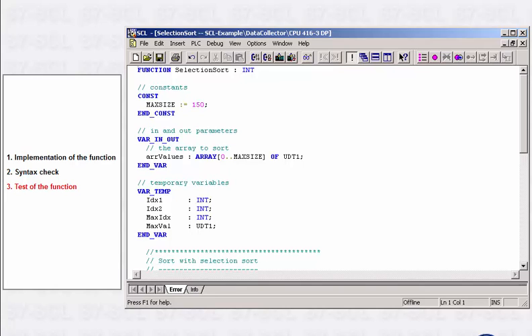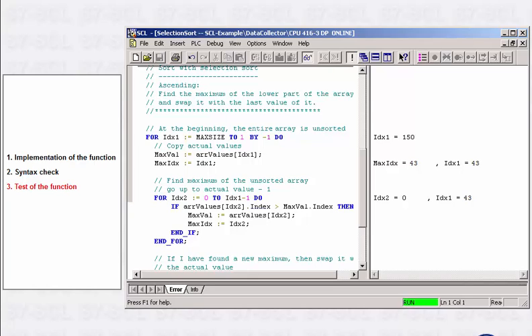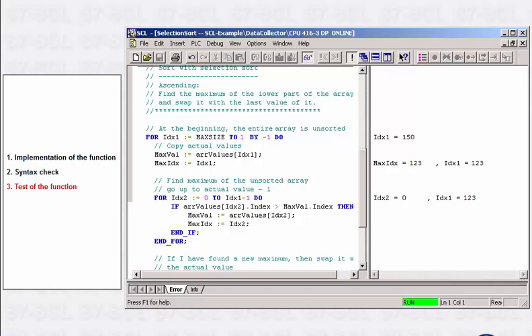To monitor the program status, you simply click on the Spectacles icon. In this way, variable assignments that occur during the block run can be observed online on the CPU. This is useful above all in finite state machines, where statuses last for several cycles. With this function, however, you can't see very much, because the changes happen so quickly.